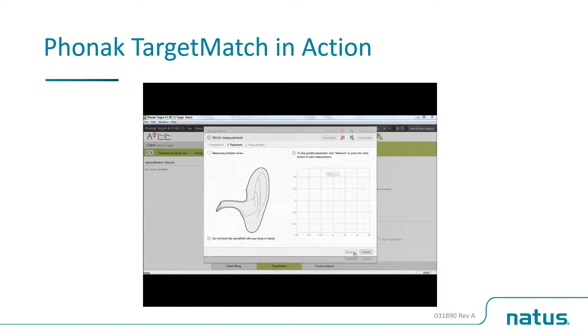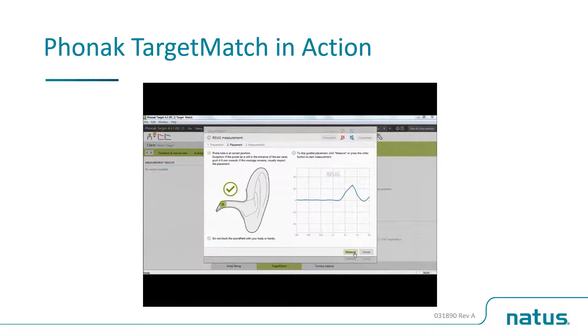One thing that you'll notice as it goes through this process is it will unmute and mute the hearing aids at the appropriate times, so you won't have to think about doing that inside the hearing aid software. Now that the unaided responses are complete, it's going to ask whether both hearing aids are inserted into the ears. Once they are, you're going to hit continue. So it's giving you time to put the hearing aids in and just giving you that gentle reminder.